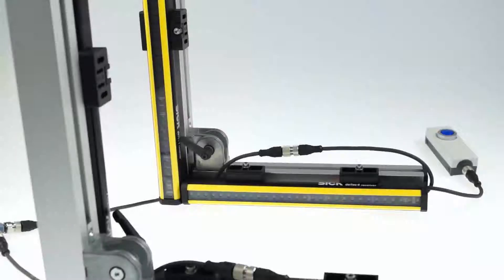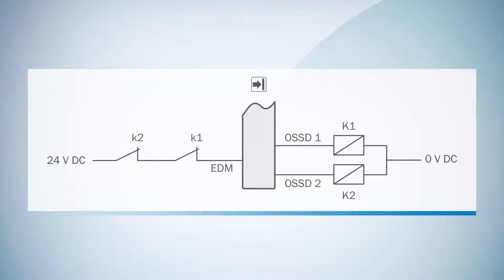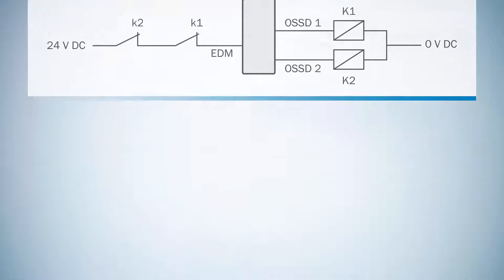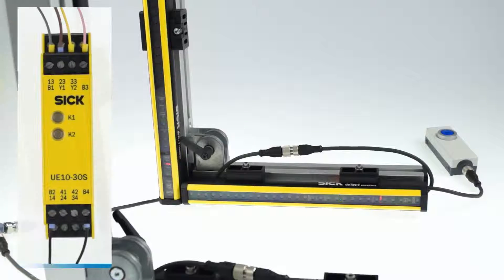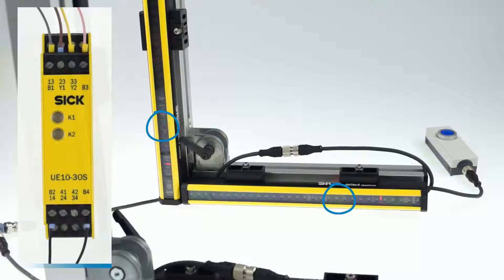The external device monitoring or EDM for short of your system is also easily configured. In the default state EDM is deactivated. Simply wire everything accordingly to the operating instructions and on the next power up the deTec4 will automatically switch into the configuration mode indicated by the green flashing field LEDs. Moreover the LED 1 of the blue alignment LEDs is flashing to show that EDM is configured now.